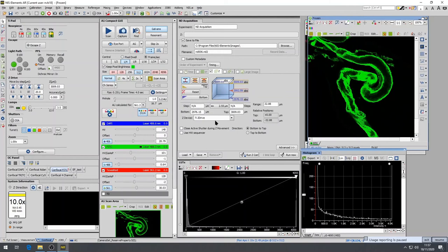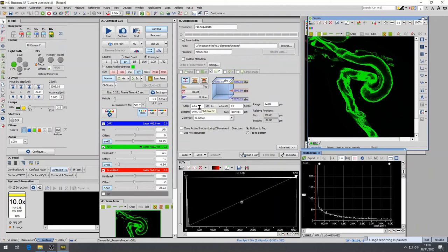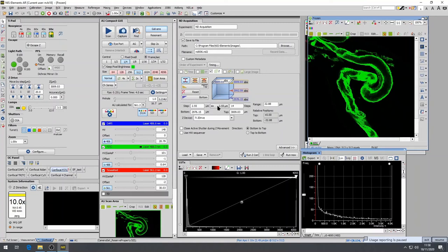The step shows you the size in micrometers that the Z-device will move in between each acquisition. Steps is the number of total Z-Stacks to be acquired. And in between the Step and Steps field lies an active button with the Z-Distance. This is similar to the Nyquist XY button found within the A1 Plus Scan area, but it applies to Z. Pressing this button will automatically adjust your step size and the number of steps necessary to complete the Z-Stack while ensuring the proper sampling frequency of your object.